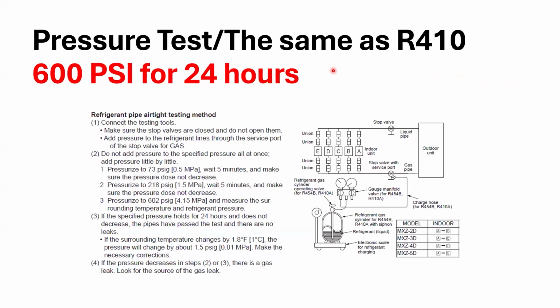So let me go back here, because people laugh at this one when they're doing the certified trainings and it's like, okay, on a 1-to-1 system, I don't have 24 hours, right? That's a 4-hour job, a 1-day job. So if you can't do 600 PSI for 24 hours, do 600 PSI and leave it on as long as you can while you do other things on that job. But soap bubble solution on all the fittings at 600 PSI should show you the smallest leak possible. So that's a way around that 24-hour requirement. But we still like power on to the system for 12 hours right before startup. So that one's tough to get around.